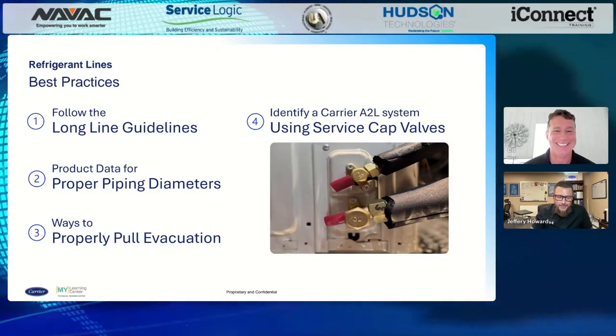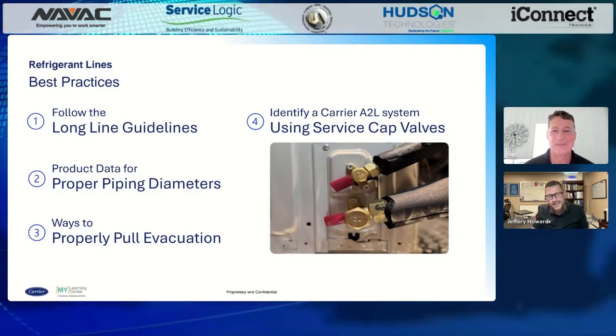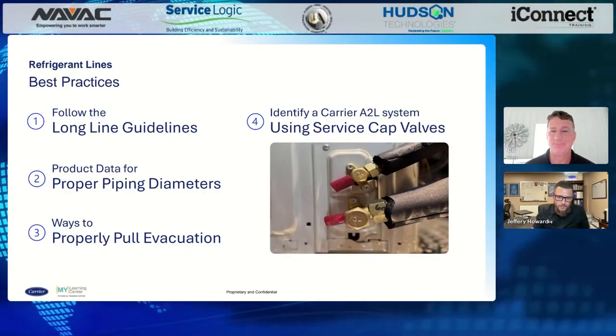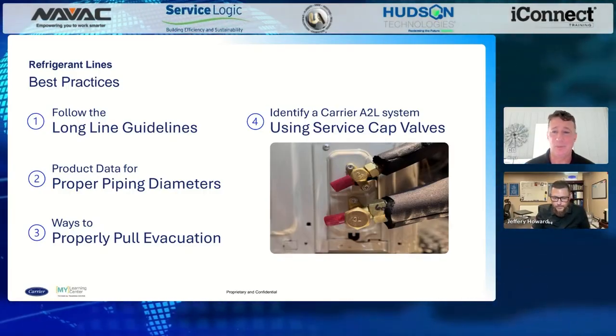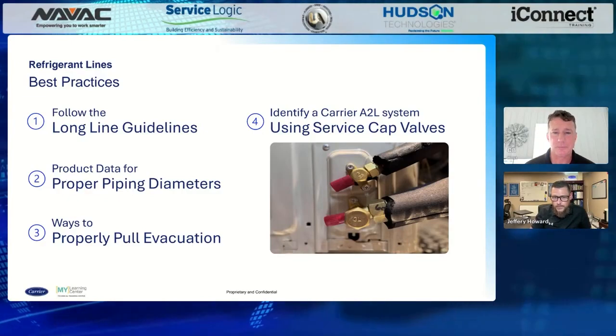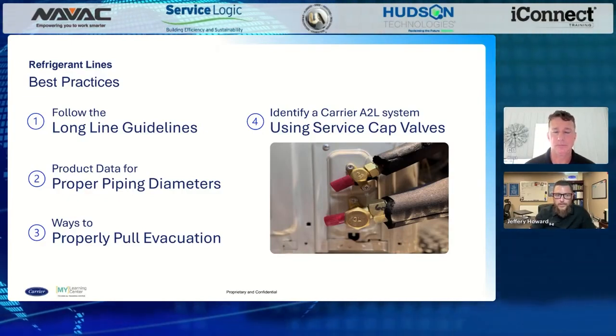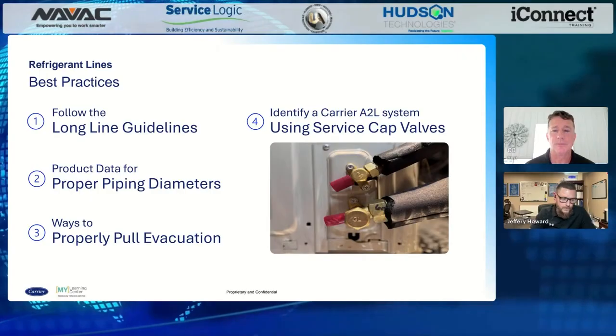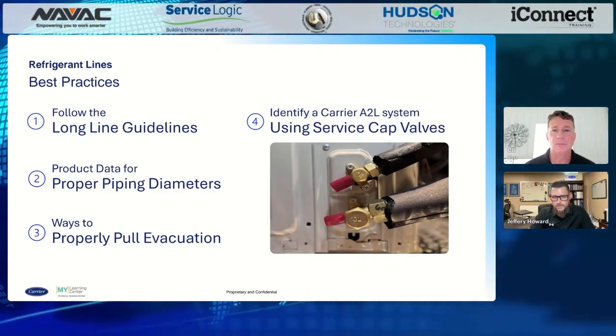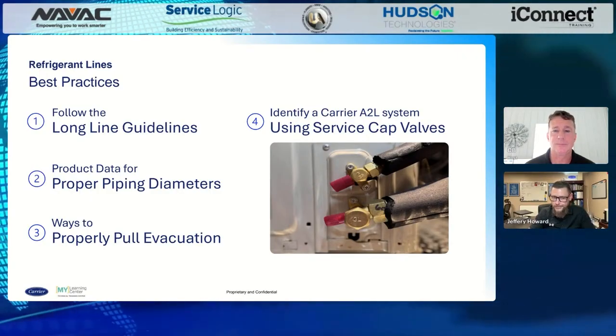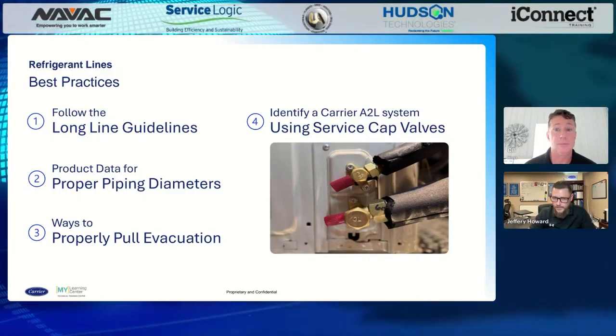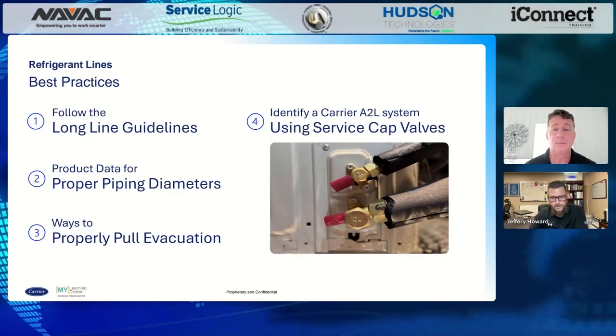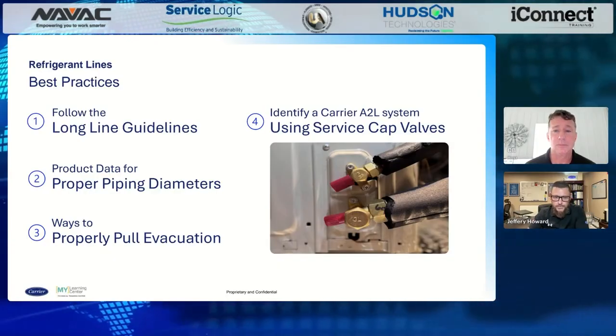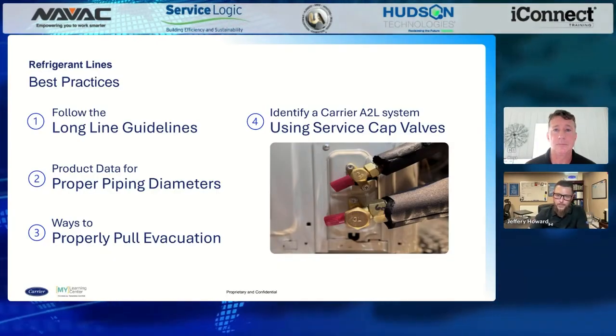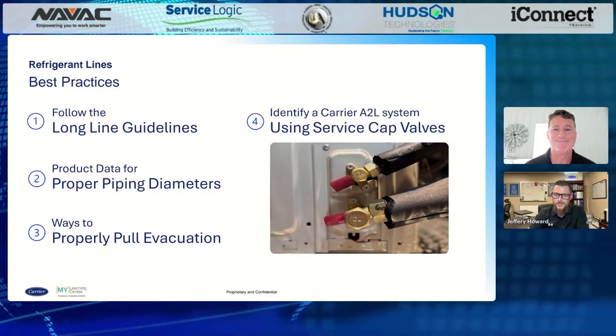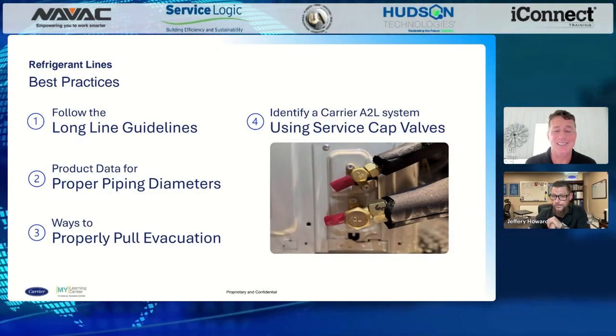A lot of people don't realize that you don't have to pull through your manifold gauges. Actually, the more connections that you have, the more potential restrictions and or leaks that you could have while you're trying to pull that vacuum on a system. So, of course, with large diameter hoses, one can suffice. Sometimes you may need two. Go directly to your suction service valve, and then on the opposite side, hook up your micron gauge on the liquid side, so you're actually getting that full evacuation through the system.